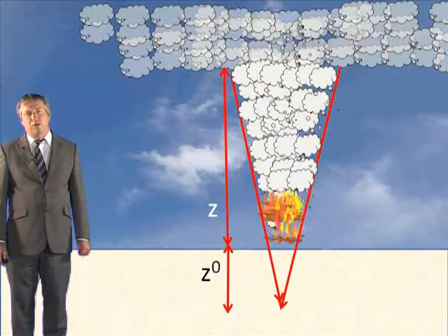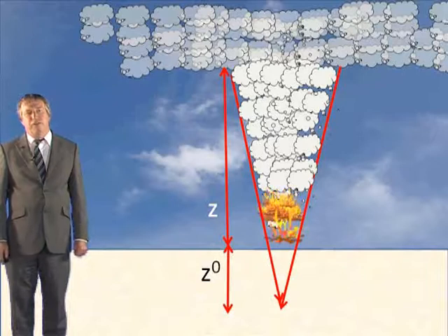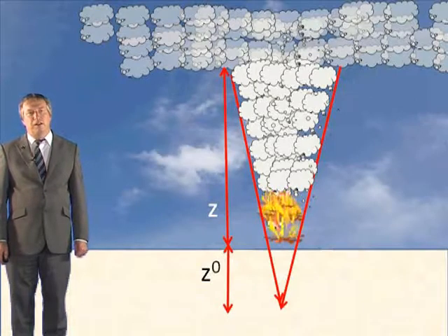The outputs for this model have been found empirically to bear a close relationship with the actual smoke flow rates. If the value of Z0 comes out to be a negative number, then the equation still holds true. What this would mean is that the virtual source of the plume is below the actual fire base, as shown here. CIBSE Guide E has one other thing to say about this second equation.